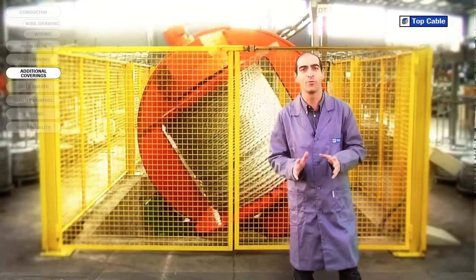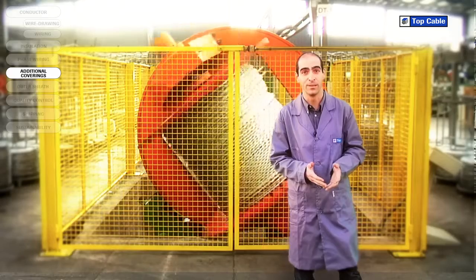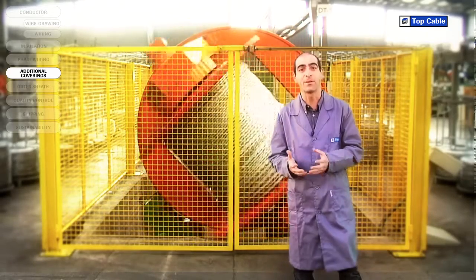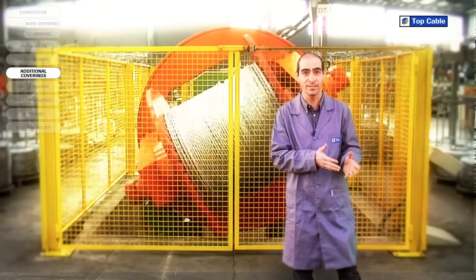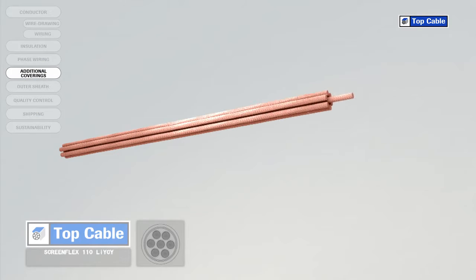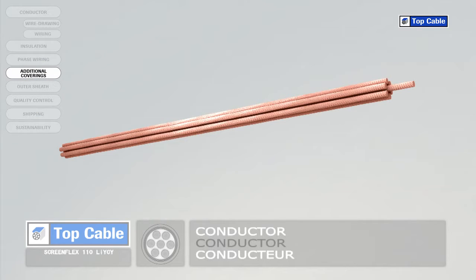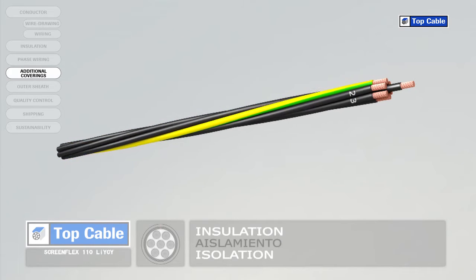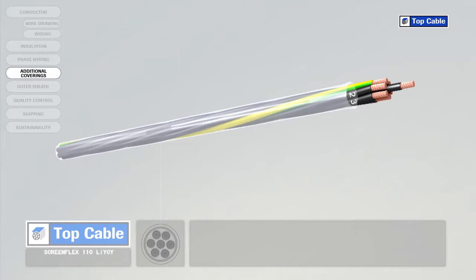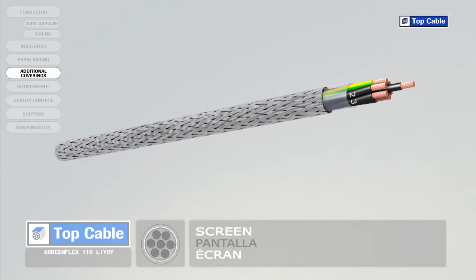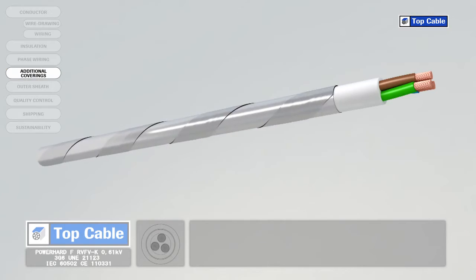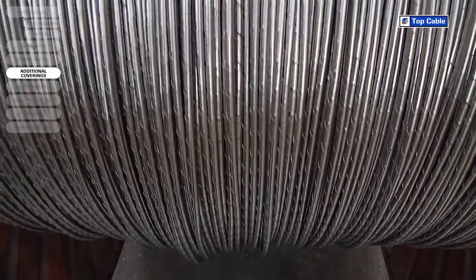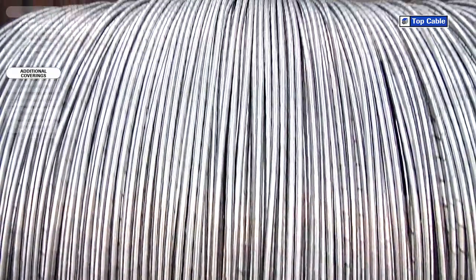That is how an electrical cable is made. However, in some cases the cable may require additional elements in order to improve its protection or operation. Electrical coverings, also called screens, insulate the signals that circulate in the cable from possible external interference. They also shield the power cables to prevent them from interfering with adjacent signal circuits. Mechanical coverings, also called armor, protect the cable from external damage that may occur from knocks, rodents, and any other potential causes of damage.